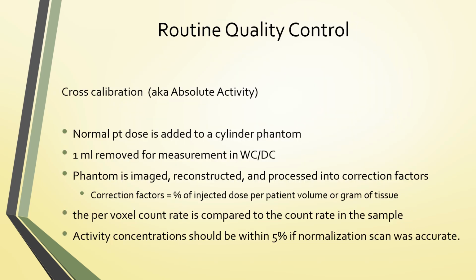So with the cross calibration, a normal patient dose is added to a cylindrical phantom. 1 milliliter is removed for measurement on the well counter or dose calibrator. The phantom is imaged, reconstructed, and processed into correction factors. Correction factors equal the percent of injected dose per volume or gram of tissue. And the per voxel count rate is compared to the count rate in the sample. That's why it is better to use a well counter for that, but you can use a dose calibrator also.